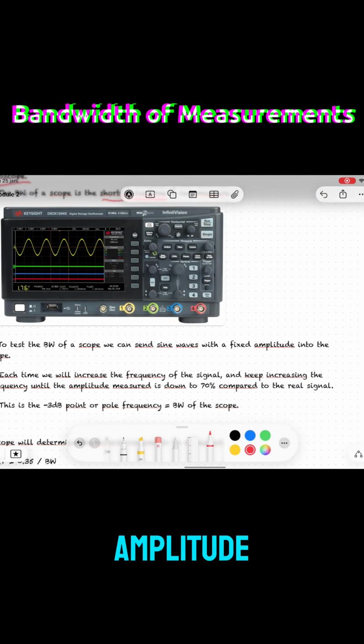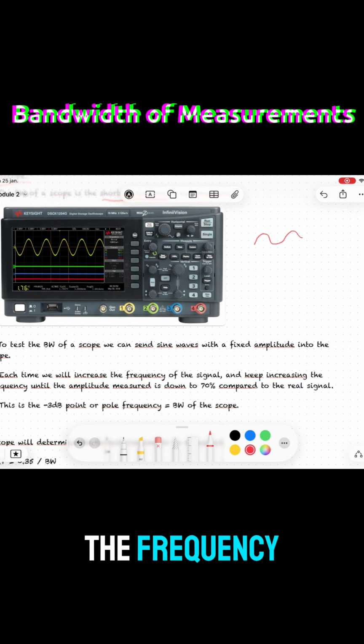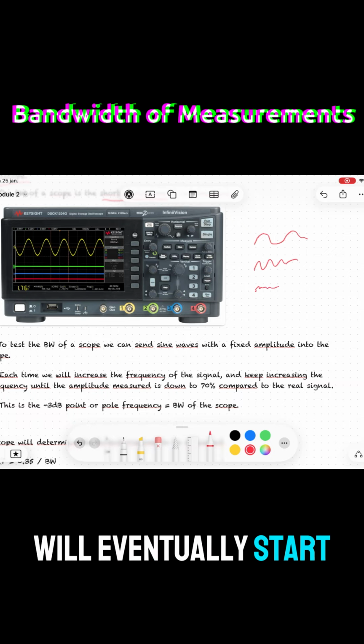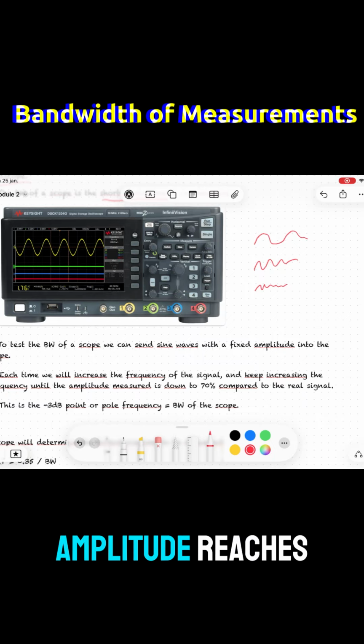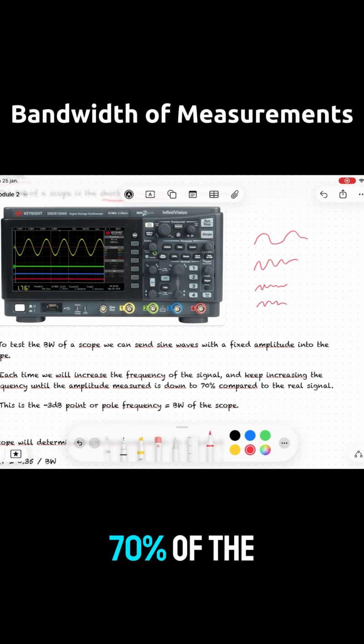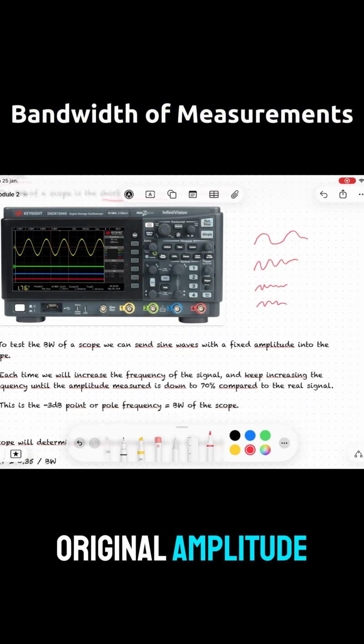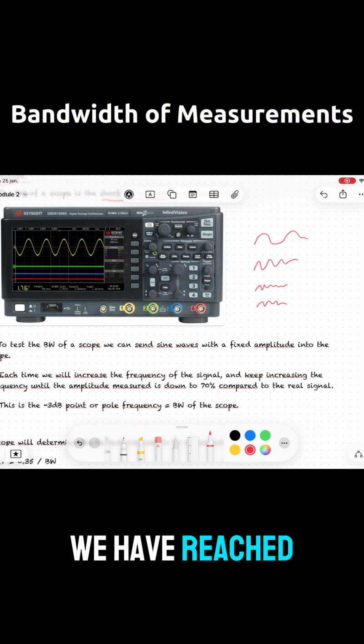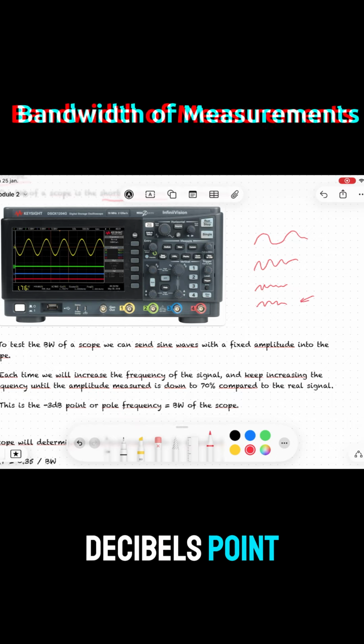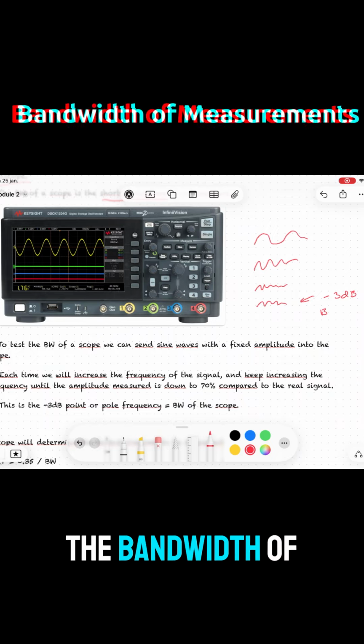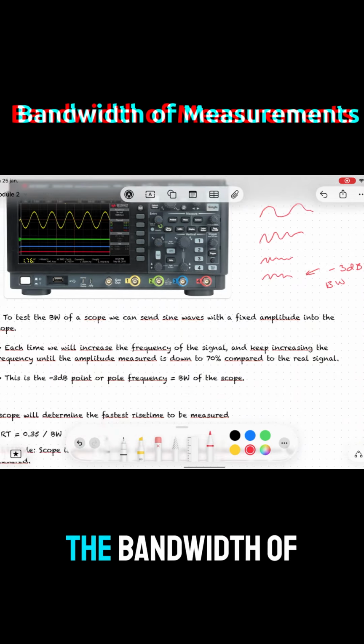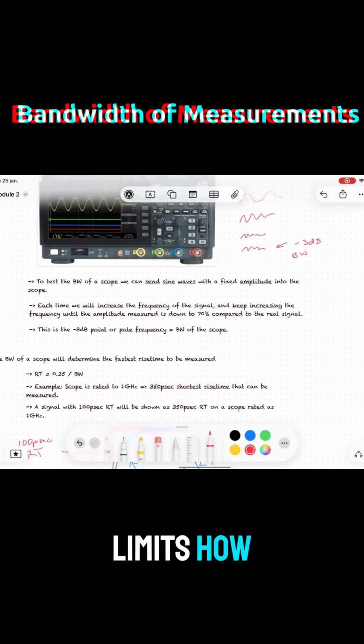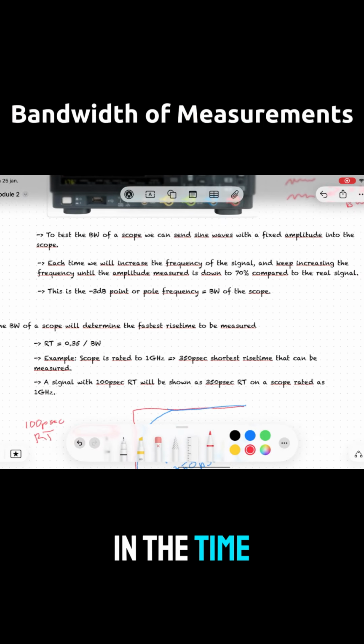with a constant amplitude and gradually increase the frequency. As the frequency increases, the measured amplitude will eventually start to drop. When the measured amplitude reaches 70% of the original amplitude, we have reached the -3 decibels point. This frequency is called the pole frequency, and it defines the bandwidth of the oscilloscope. The bandwidth of the scope directly limits how fast an edge it can resolve in the time domain.